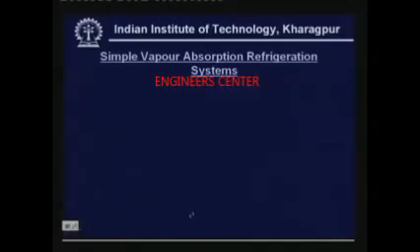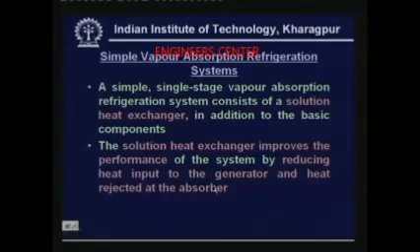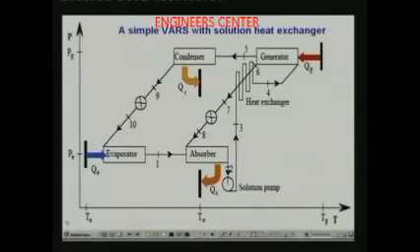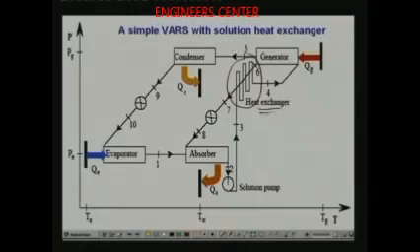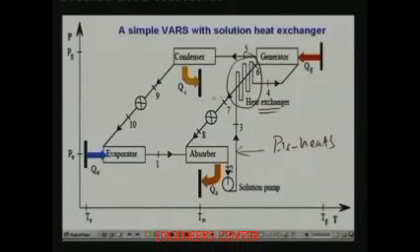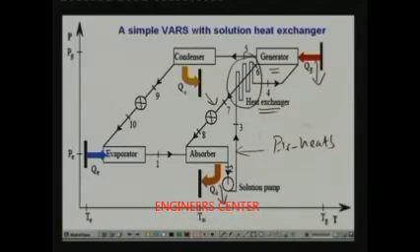A simple single-stage vapor absorption refrigeration system consists of a solution heat exchanger in addition to the basic components. The solution heat exchanger improves performance by reducing heat input to the generator and heat rejected at the absorber. This extra component preheats the solution going to the generator by using the heat of the solution coming from the generator, creating a heat exchange between the hot solution leaving the generator and the cold solution entering it. As a result, Q_G and Q_absorber are both reduced.